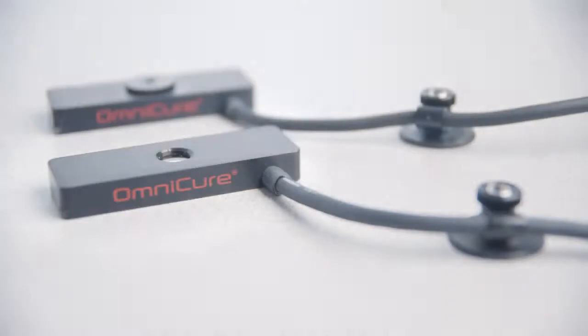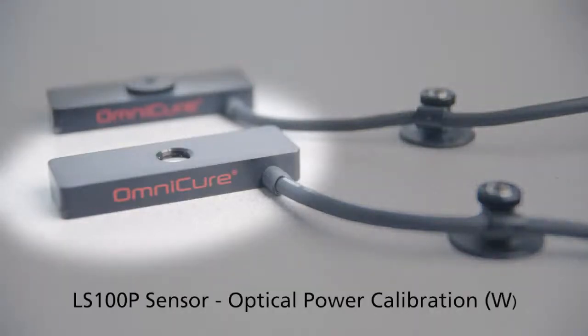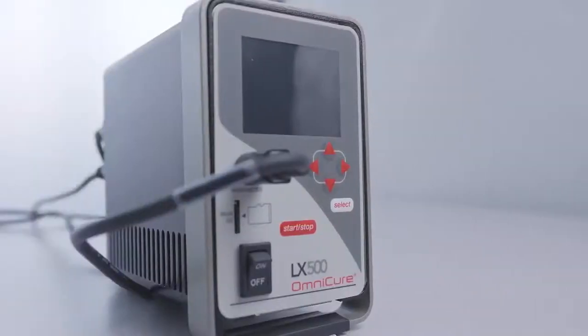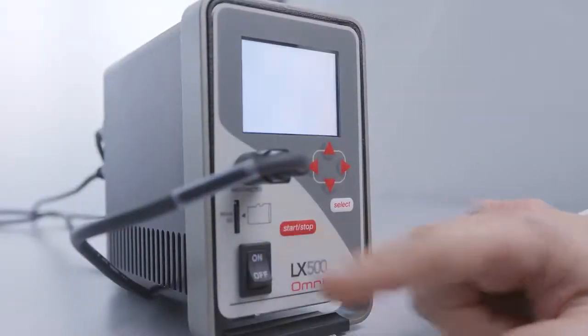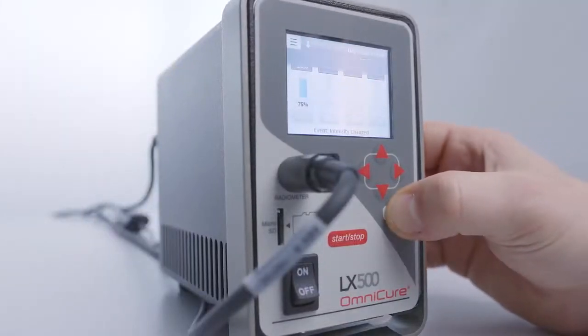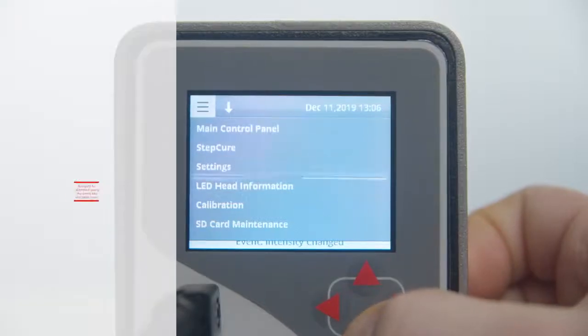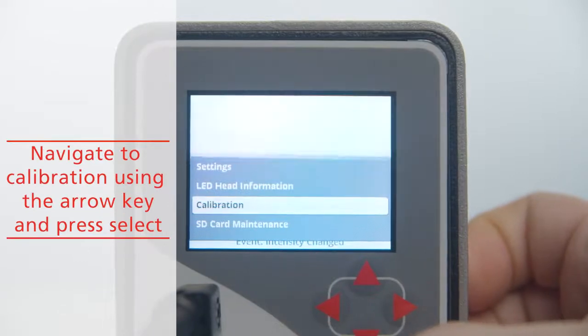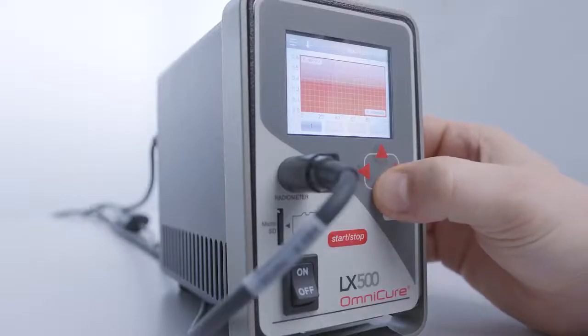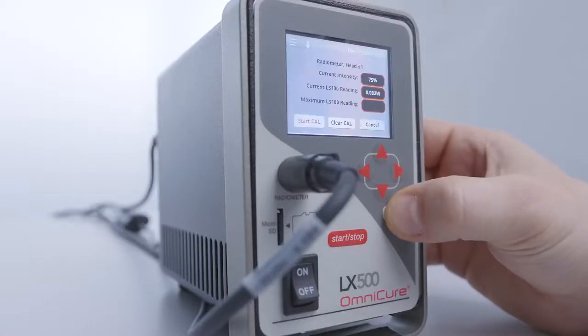Once the power calibration kit using the LS100P sensor has been assembled and connected to the LX500 controller along with the LED head, the LX500 controller can be turned on and calibration can be initialized. Starting from the home screen, access the calibration by pressing Select, and navigate to Calibration using the arrow key and press Select. Choose the LED head you wish to calibrate with the arrow keys and press Select. Calibration needs to be done individually for each connected LED head.